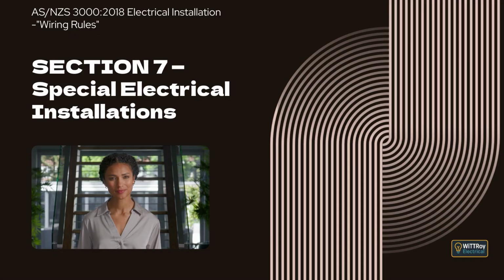Clause 7.2.3 Main switchboard and switchgear. This clause explains that special arrangements are required for switchboards and switchgear supplying safety services so that faults in the general installation do not affect critical safety equipment. Clause 7.2.3.1 General. This clause explains that each safety service must be controlled by a main switch that is separate from the switches used for the rest of the installation and from switches used for other safety services.